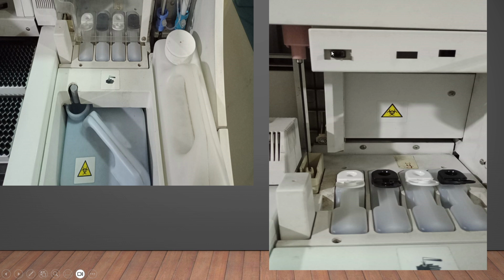But do remember, this door also has got a sensor. So when the instrument is working and you suddenly open this door, the instrument is going to stop and all the tests are going to get cancelled. So this is the procell clean cell. Okay, this is how it is placed, and it has got its own incubator to make sure that these procell clean cells are at 22 degrees centigrade.